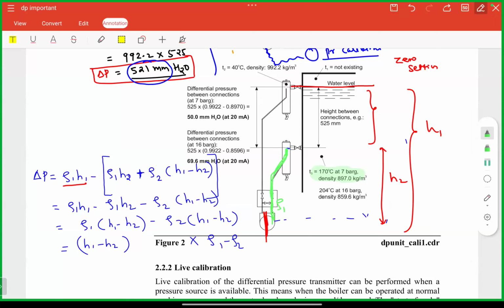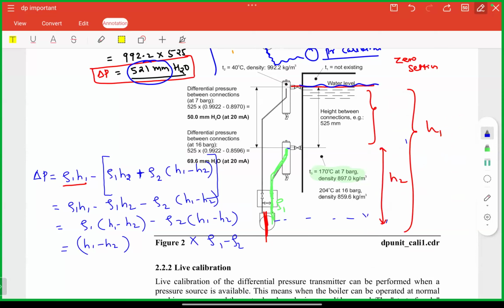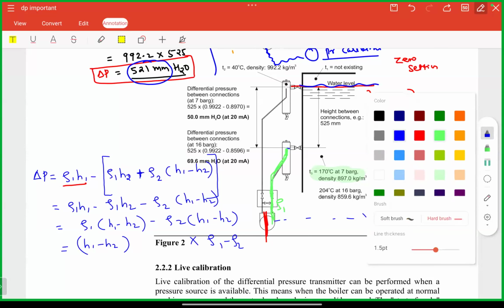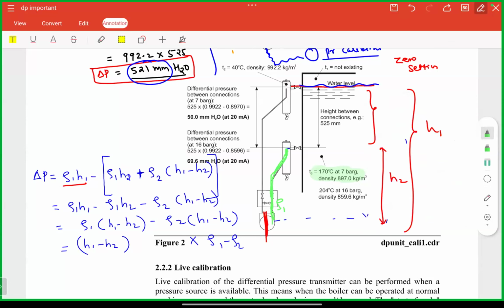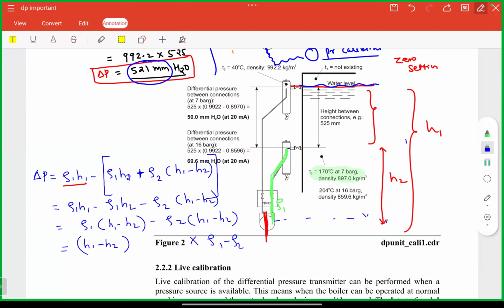So what are you doing, bhaiya? You are assuming your water level is up to this point. That means there will be two heads acting. One, the head acting in the variable leg. What will be the density of that head? That will be density 1 only, because that pipe is outside the boiler and exposed to atmospheric condition. But there will also be an additional head here.